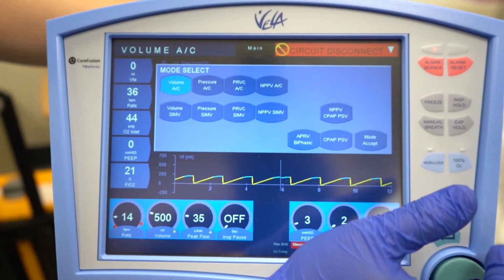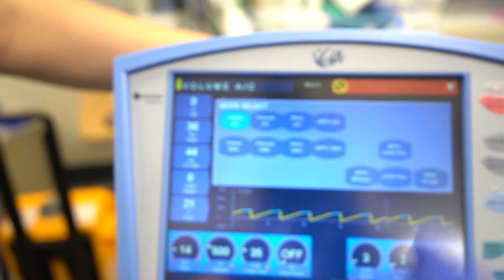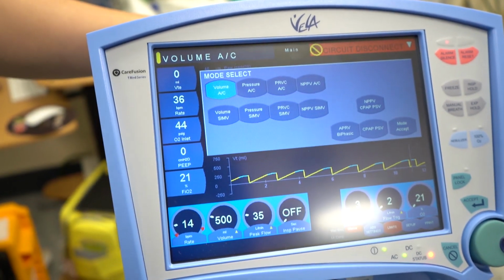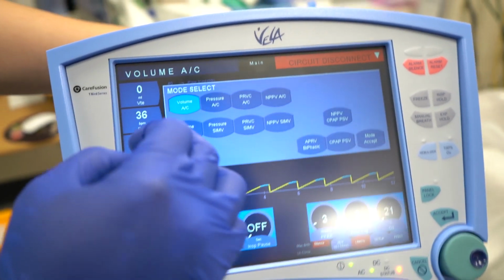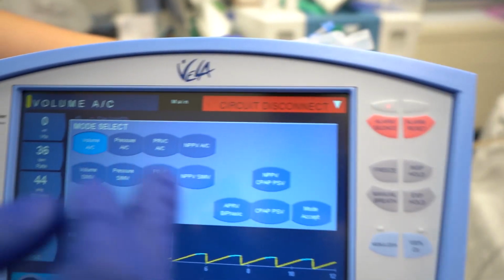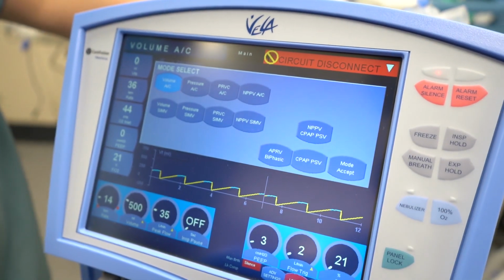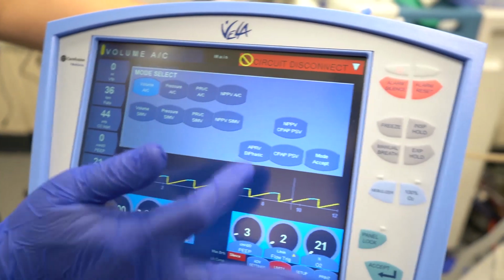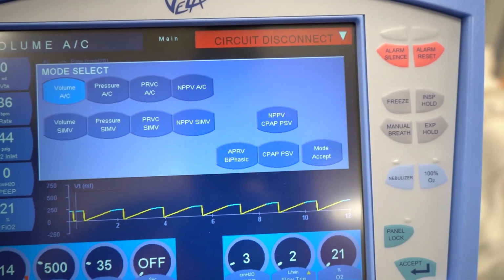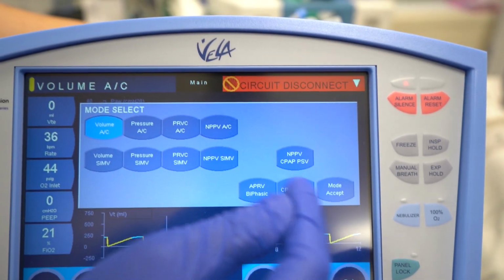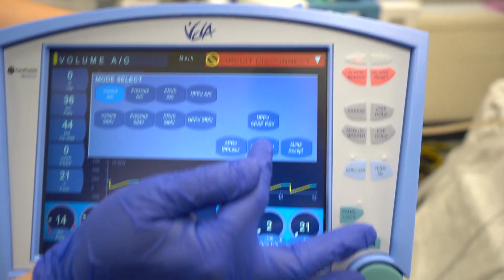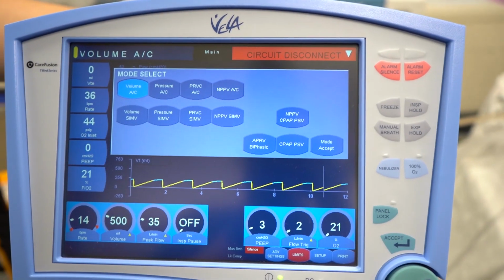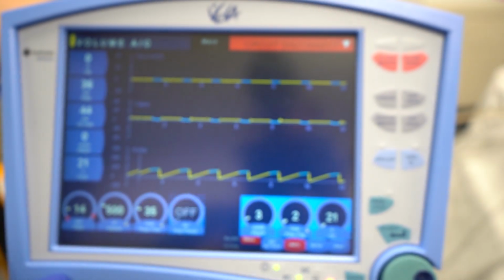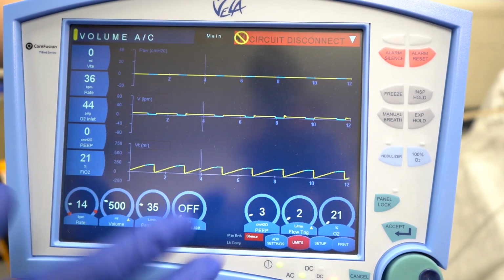You've got volume control AC, pressure AC, PRVC. Your non-invasive will be indicated by NPPV AC, so non-invasive positive pressure ventilation. Then you have SIMV with the same volume, pressure, PRVC, non-invasive. Your bi-level or APRV is located on the bottom, APRV biphasic, and your pressure support, when you're weaning the patient, pressure support CPAP is located on the bottom here as well. Okay. So select your mode, accept, and it brings you back to the original screen.